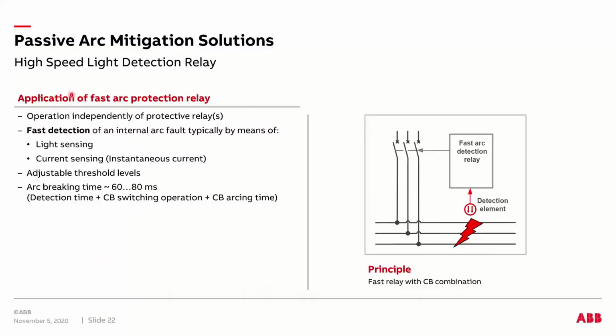So one of the other passive arc mitigation solutions is using a light detection relay, right? So one of the advantages is it's a very, very fast acting device that is exclusively used for an arc flash incident in your equipment, right? So you can use two parameters, right? So one of them is the light sensing, and the light sensing is a differentiator because when you have an arc flash in your equipment, it creates a light intensity that is 5,000 times brighter than the natural light, right? So it can be easily differentiated between an arc flash incident as compared to just an exposure to an outdoor environment, right?